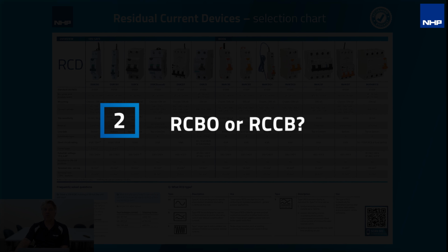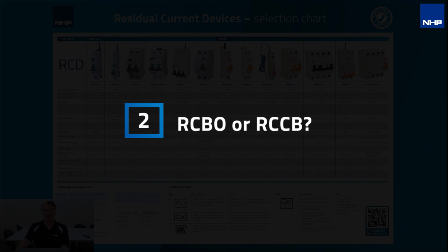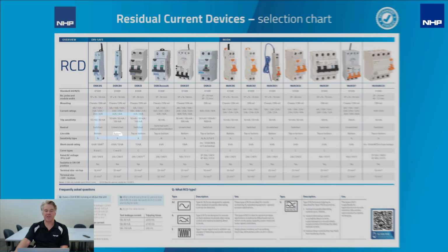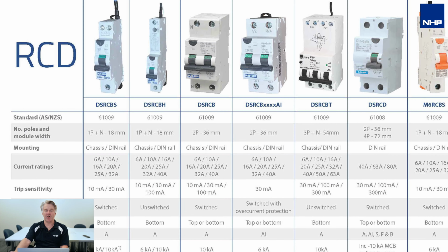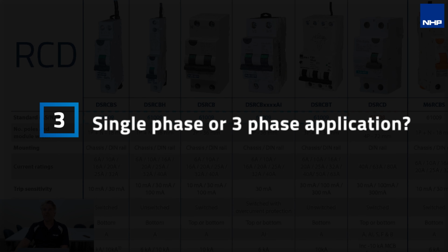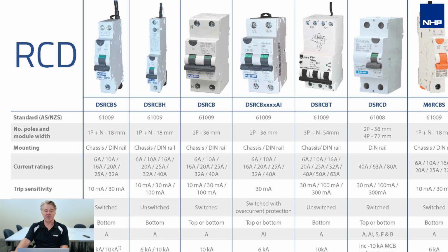The next selection, do you require an RCBO or an RCCB? So RCBOs typically have a standard of 61009, as you can see here on the top line, or 61008 for RCCBs. So RCCBs don't provide overcurrent protection, where RCBOs do. Then the next one is, is it for a single phase application or a three-phase application? So you can see next on the line here, you can see 1 pole plus neutral, or a 2-pole device, or 3-pole plus neutral.